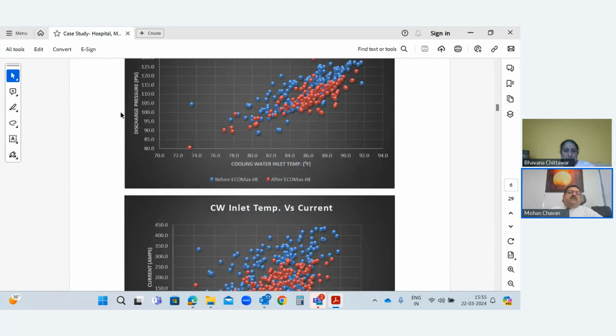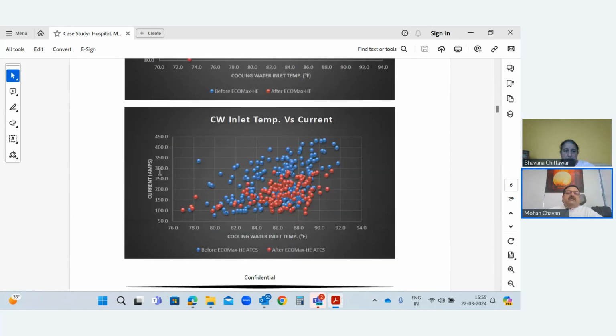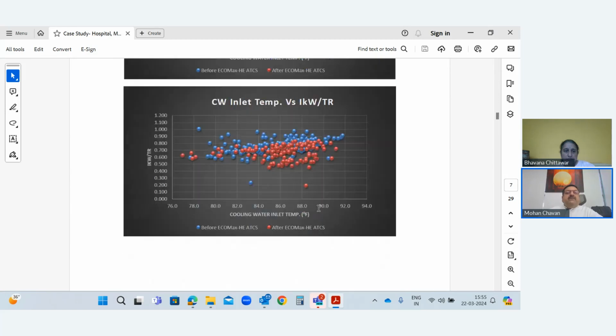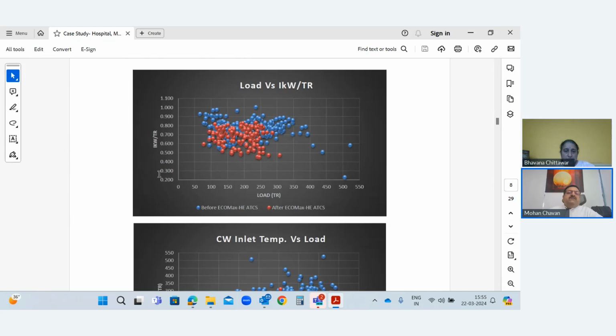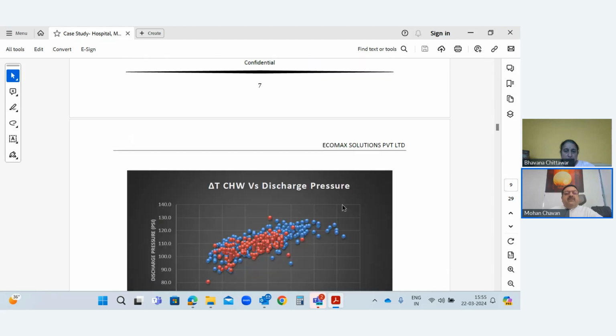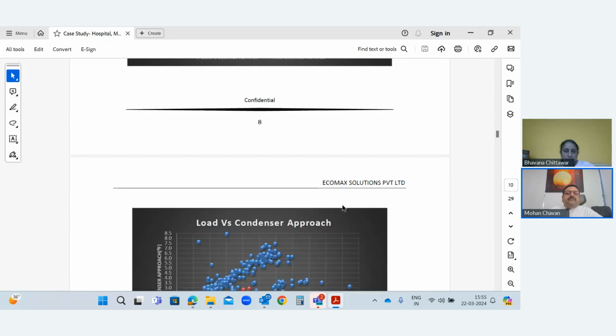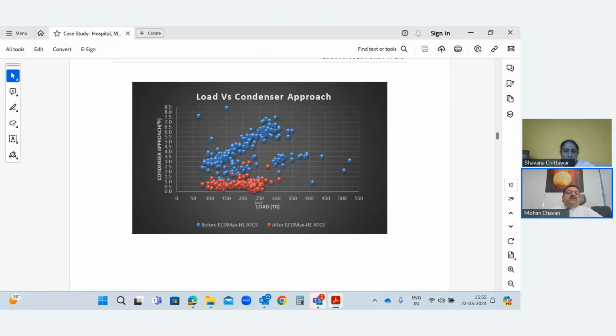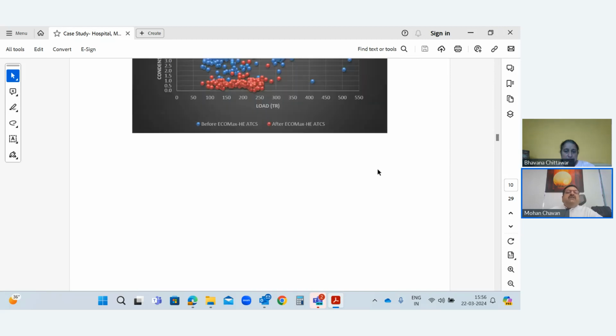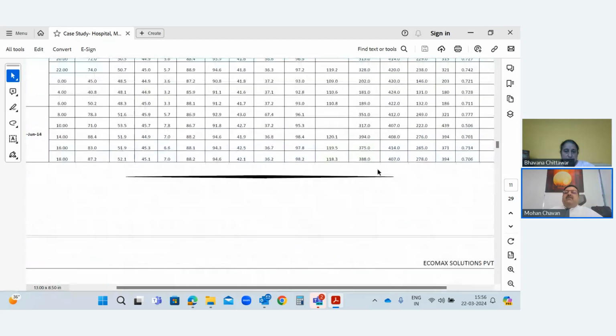So these are some of the trends. We plotted discharge pressure versus cooling water inlet, amperes versus cooling tower inlet temperature, etc. This is percentage load versus IKW per TR, load versus IKW per TR. So this is after. You can clearly see a difference of IKW per TR before and after implementation. This was a condenser approach, load versus condenser approach. So after implementation of automatic tube cleaning system, these red ones, it's about below 1 degree F roughly, and before it used to go even up to 7 degree F. So this is how they have saved substantially on the energy costs. And this is the backup data we have for it.